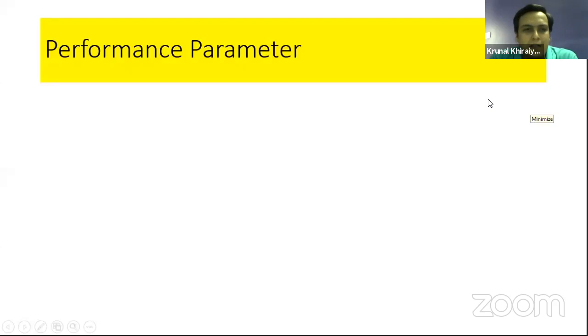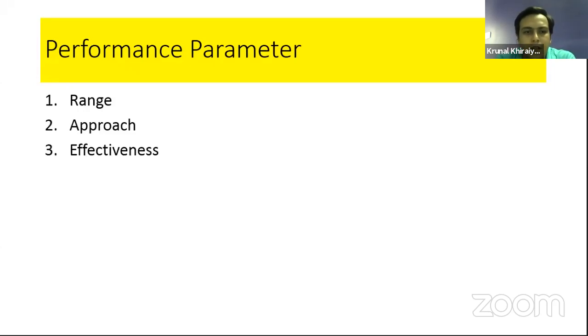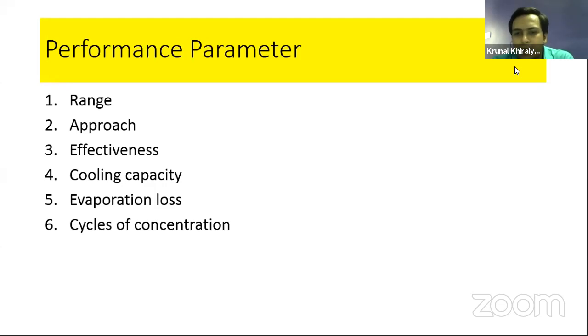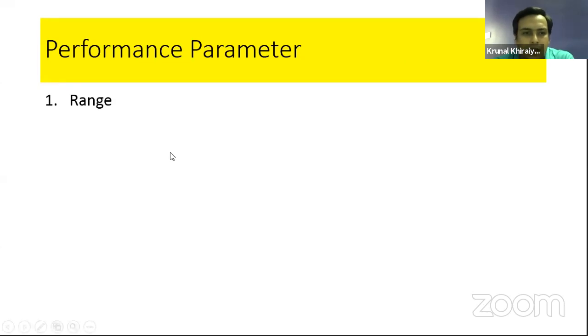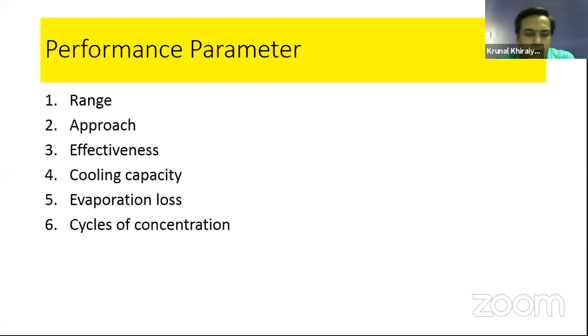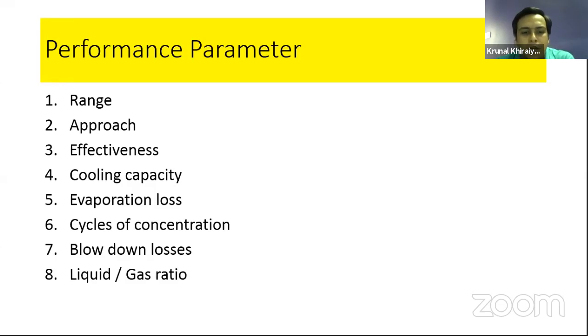Now the next task after gathering the different parameters: what are the different performance parameters of a cooling tower on the basis of which we can reach some conclusions? So now I'm going into the performance parameters. They are the range of the cooling tower, approach, effectiveness, capacity, evaporation losses, cycle of concentration. Yes, someone is asking about evaporation; we will come back to the COC later on. It is a very important point of discussion in today's presentation. Then blow down losses, and very important, the liquid to gas ratio. These are the performance parameters on the basis of which we can check whether our cooling tower is performing well or not.